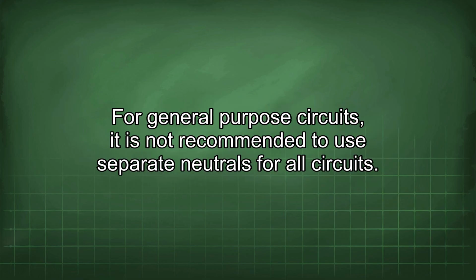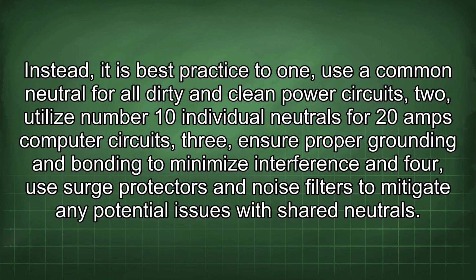In this case, separate neutrals can help mitigate these effects. For general-purpose circuits, it is not recommended to use separate neutrals for all circuits. Instead, it is best practice to: 1. Use a common neutral for all dirty and clean power circuits. 2. Utilize number 10 individual neutrals for 20 amp computer circuits. 3. Ensure proper grounding and bonding to minimize interference. And 4. Use surge protectors and noise filters to mitigate any potential issues with shared neutrals.